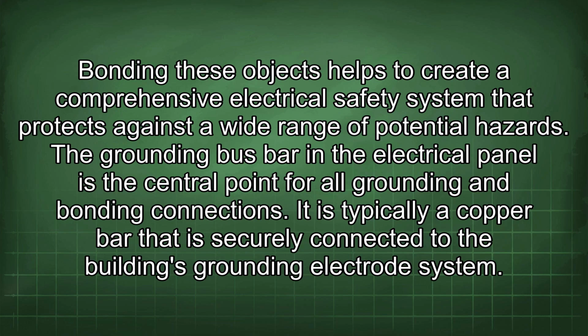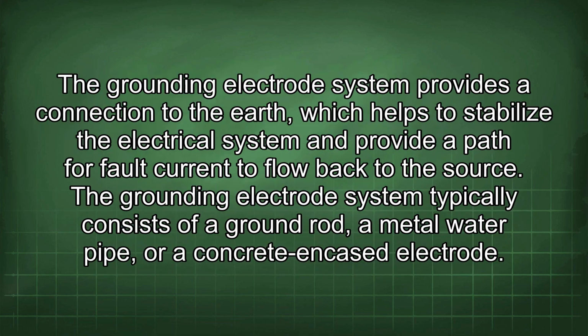The grounding bus bar in the electrical panel is the central point for all grounding and bonding connections. It is typically a copper bar that is securely connected to the building's grounding electrode system. The grounding electrode system provides a connection to the earth, which helps to stabilize the electrical system and provide a path for fault current to flow back to the source.